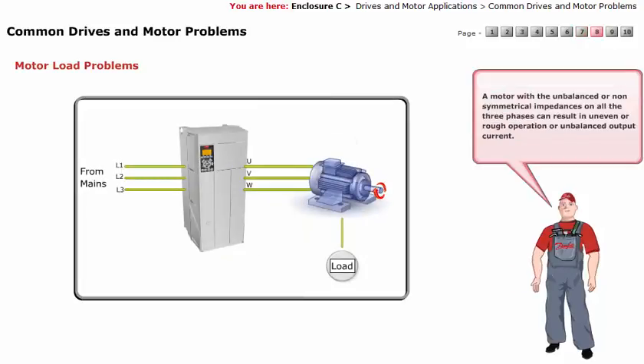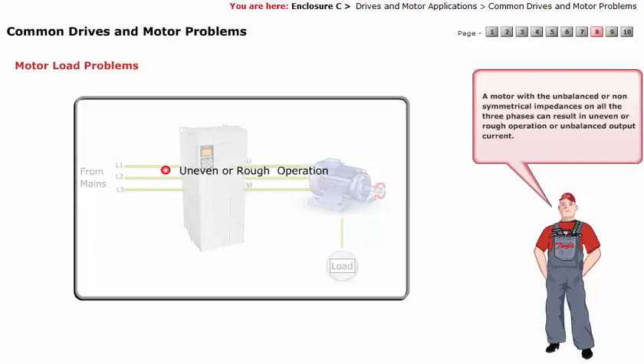A motor with unbalanced or non-symmetrical impedances on all three phases can result in uneven or rough operation, or unbalanced output current.